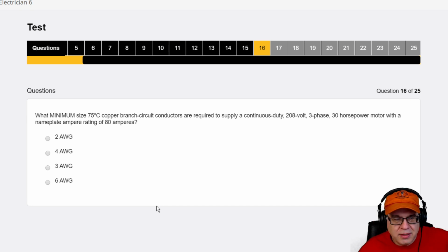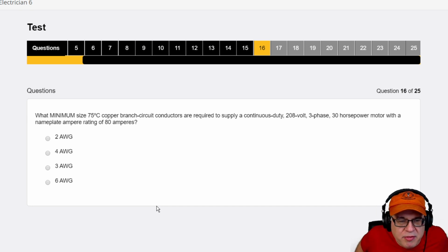All right. Now, what is the minimum size 75 degree C copper branch circuit conductor required to supply a continuous duty 208 volt 3-phase 30 horsepower motor with a nameplate ampere rating of 80 amperes? Wow. Okay. All right, guys, we're sizing conductors here. Remember, if you watched my motor video, this should be pretty easy for you. What do we have to do?